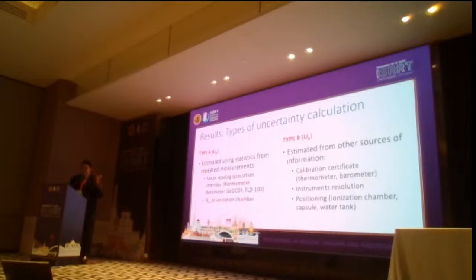So in terms of uncertainty, that's what we come back to, the main topic. We are using 2 types of uncertainty, type A and type B. Basically, type A uncertainty is inherent random from the statistical analysis, where we measure the data and calculate the standard deviation. Meanwhile, type B uncertainty is very subjective. It accounts for several systematic effects coming from the process. For type A, it comes from the ionization chamber reading, thermometer reading, barometer, and also the dosimeter reading. And for type B, it's coming from the calibration certificate, instrument resolution, and also the positioning of the water tank together with the positioning of the dosimeter.